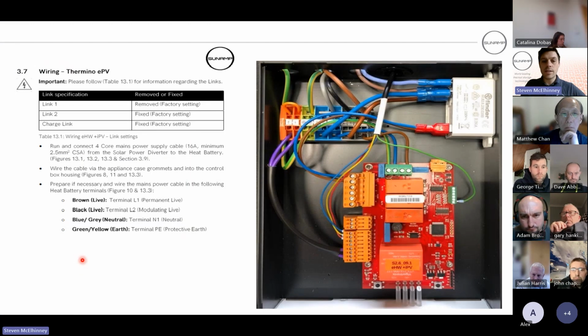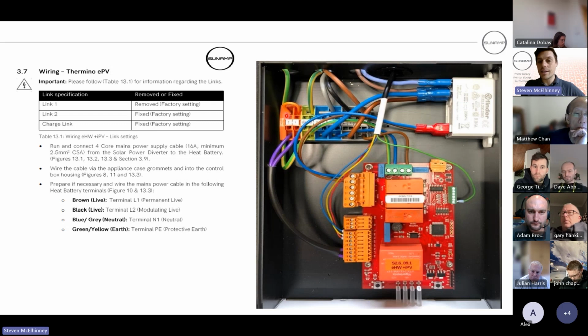Your ePV, it's a little bit different. You can see we've got a 4-core flex here. So you've got a permanent live, a switch live or a modulating live, a neutral, and an earth. And you can see that charging link is in play as well, constantly fitted, because we need to complete that control circuit so the unit can tell itself that it's available for solar, basically. So if you don't want to remove that, just keep that in.